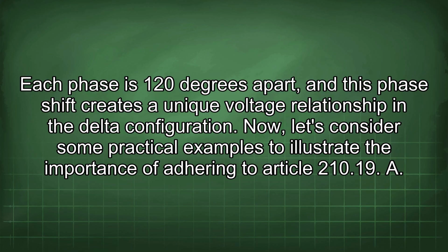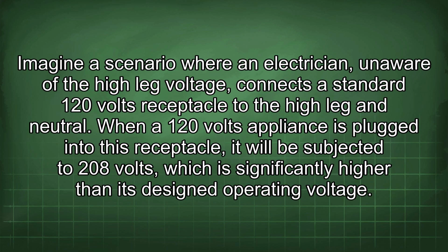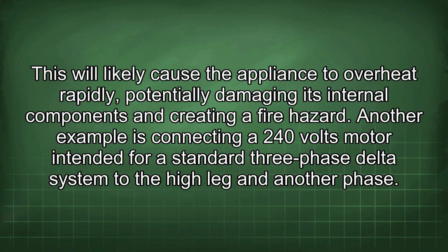Now let's consider some practical examples to illustrate the importance of adhering to Article 210.19. Imagine a scenario where an electrician, unaware of the high leg voltage, connects a standard 120 volts receptacle to the high leg and neutral. When a 120 volts appliance is plugged into this receptacle, it will be subjected to 208 volts, which is significantly higher than its designed operating voltage. This will likely cause the appliance to overheat rapidly, potentially damaging its internal components and creating a fire hazard.